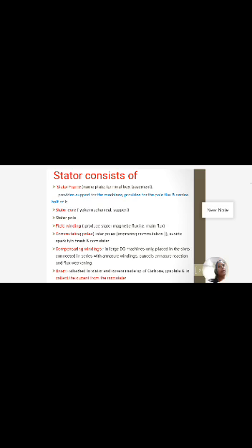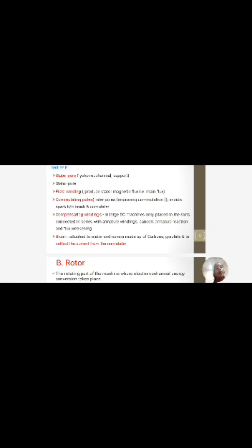Okay, next part is brushes and brush gear. We can see the brush box on the external circuit of the DC machine, and the function is to collect current from the commutator and make it available to the stationary external circuit. And coming to the choice of materials, brushes are normally made up of soft material like carbon. Next, bearings. Ball bearings are usually used, and generally roller bearings we can also prefer. So this is about the construction of a DC generator, or the general construction of a DC machine.